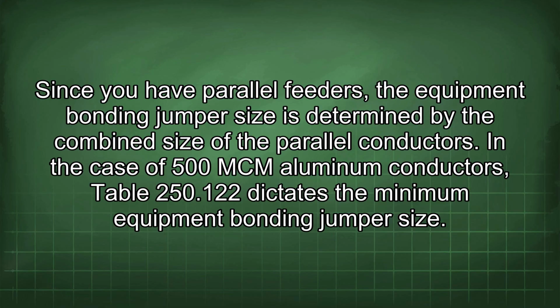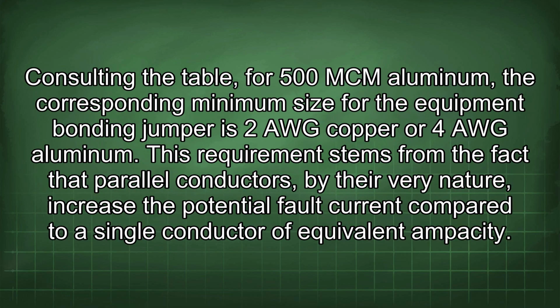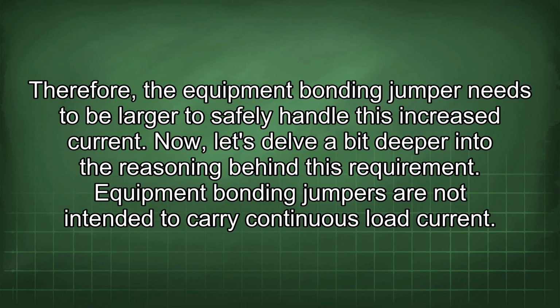In the case of 500 mcm aluminum conductors, Table 250.122 dictates the minimum equipment bonding jumper size. Consulting the table for 500 mcm aluminum, the corresponding minimum size for the equipment bonding jumper is 2 AWG copper or 4 AWG aluminum. This requirement stems from the fact that parallel conductors, by their very nature, increase the potential fault current compared to a single conductor of equivalent ampacity. Therefore, the equipment bonding jumper needs to be larger to safely handle this increased current.